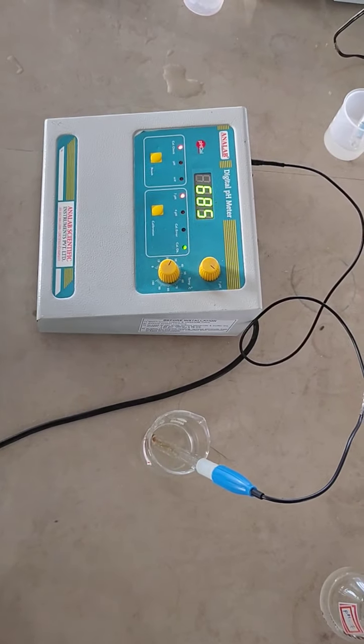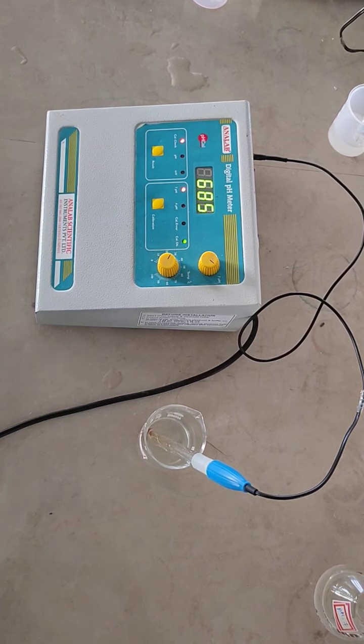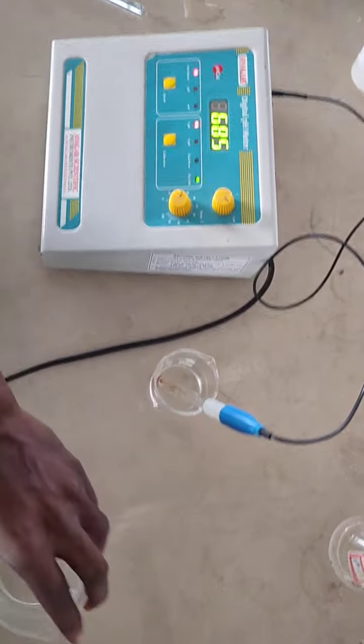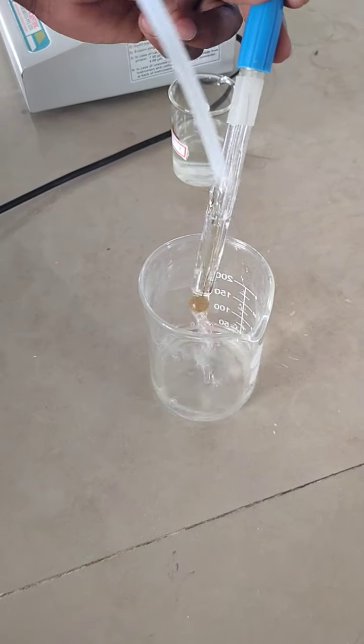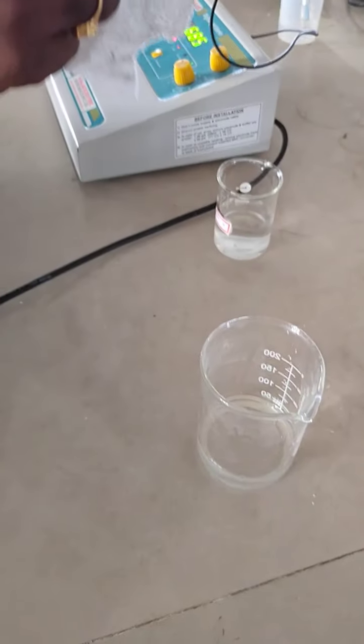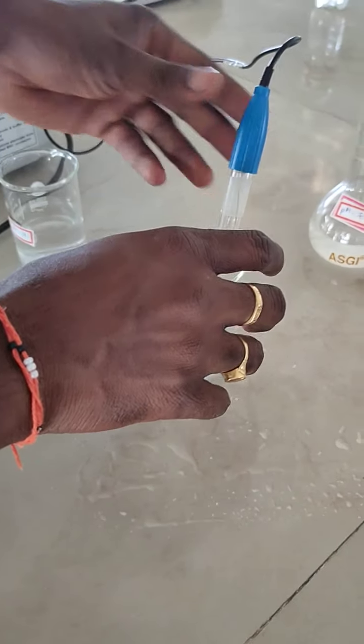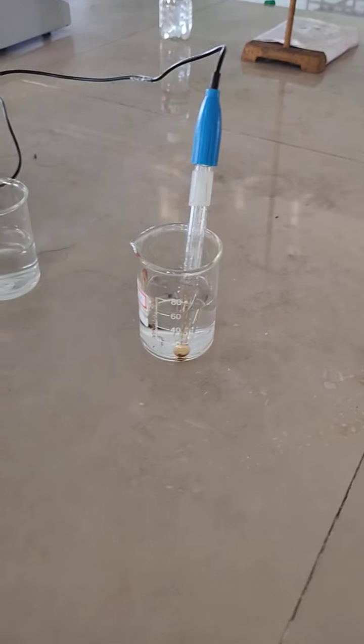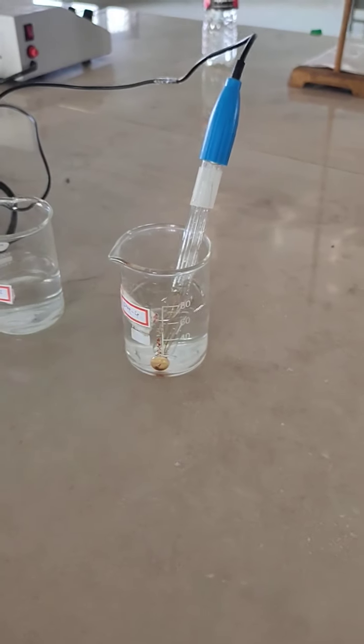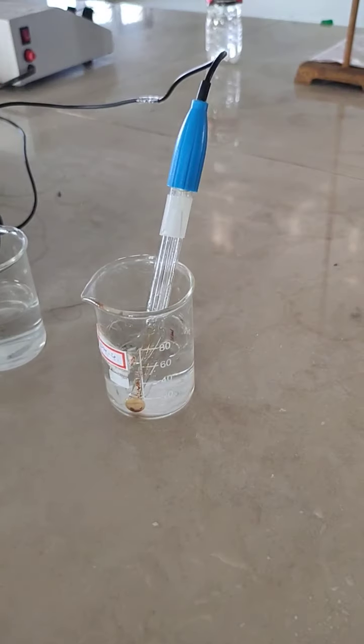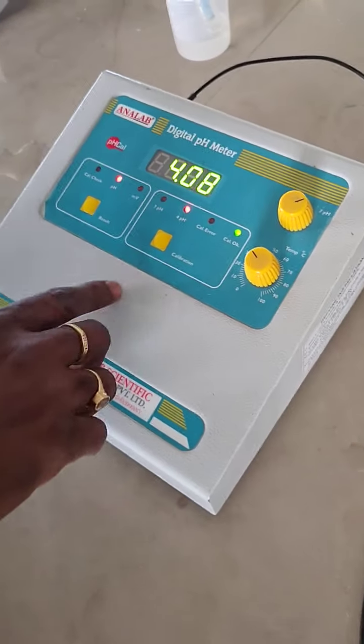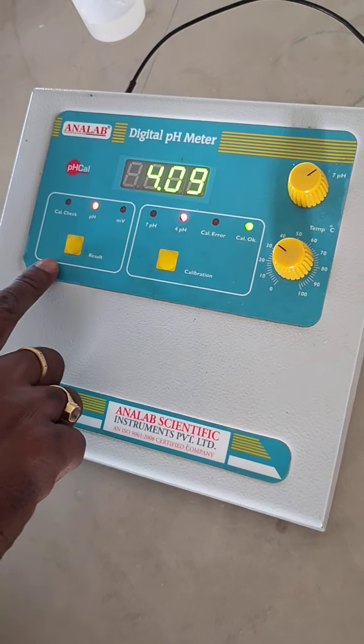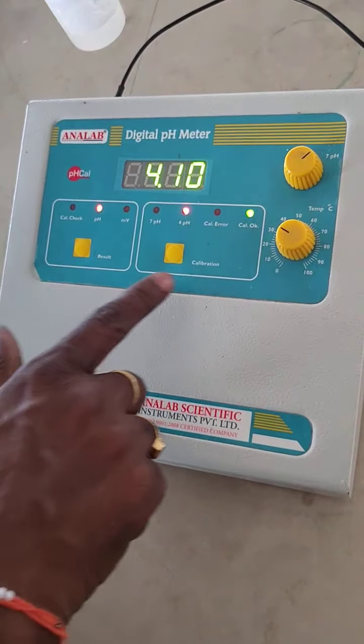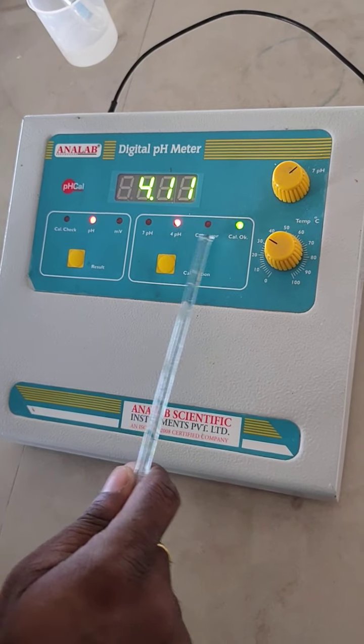The meter reads the value of 7. Okay, then after cleaning this electrode with distilled water, clean the electrode thoroughly with distilled water. Then put this electrode in pH 4 buffer solution. So it is the pH 4 buffer solution. The electrode is dipped in pH 4 solution and here, see here, so put the calibration button in 4 and result in pH, then it shows calibration okay, there is no error here.